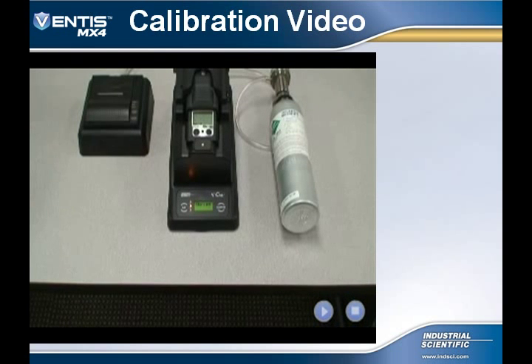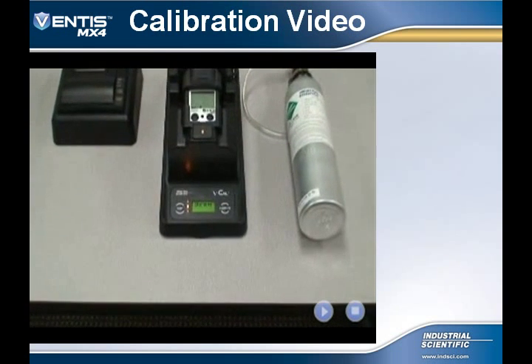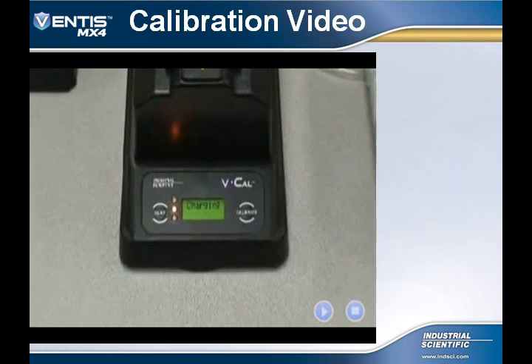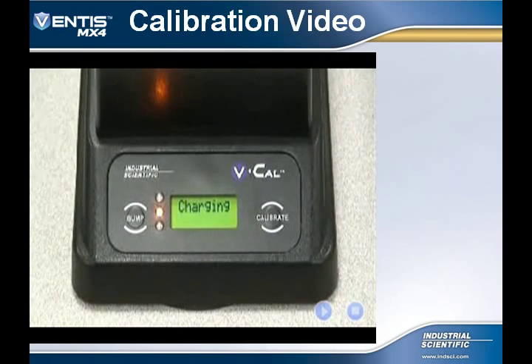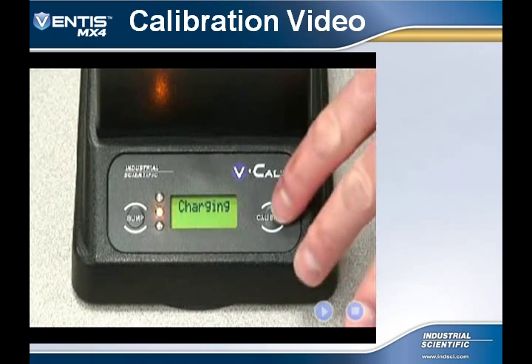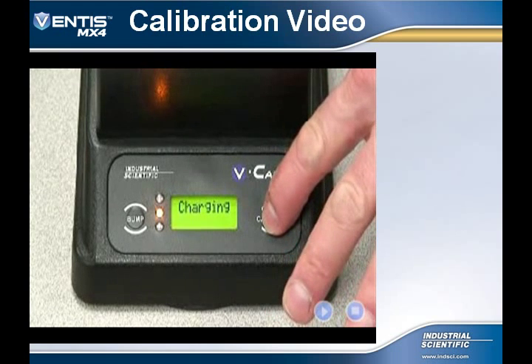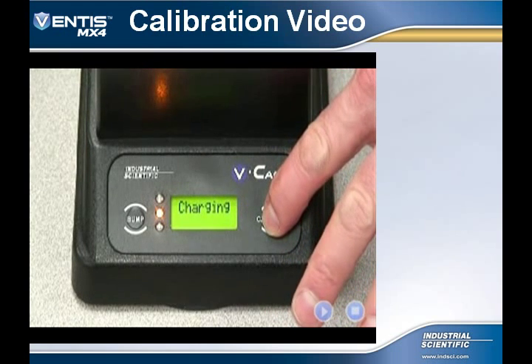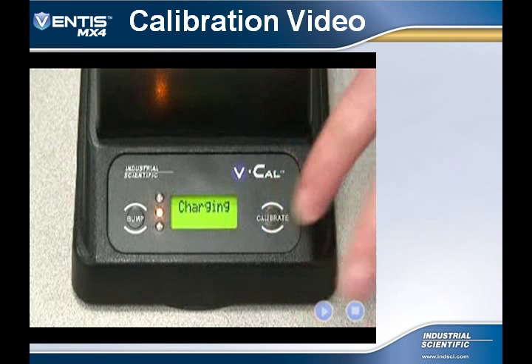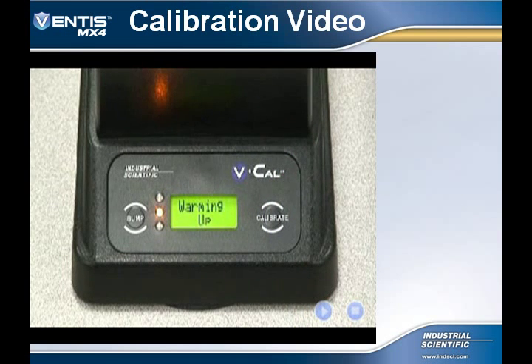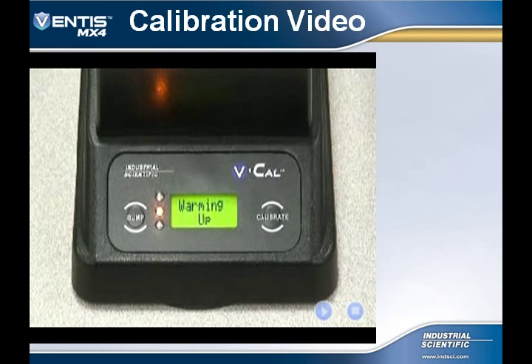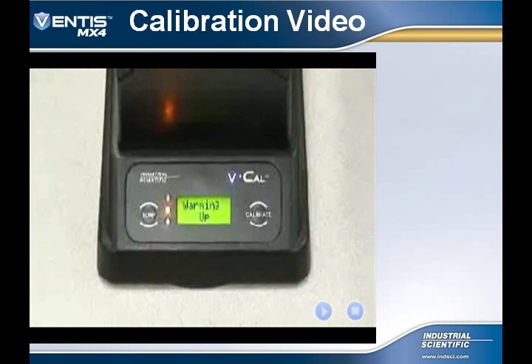This video will walk you through the calibration of the VCal. With the Ventis MX4 installed into the VCal, press and hold the Calibrate button for approximately 3 seconds. The VCal will turn the instrument on and the display will toggle between warming up and Ventis MX4.